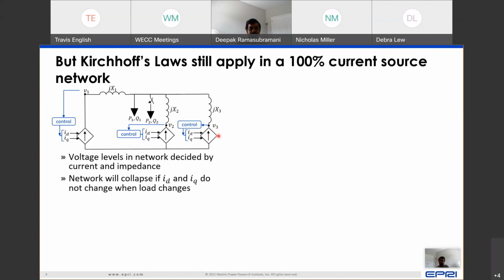But at the same time, if you have a change in the network, say something like a load increase, where you change the topology of the network, you change the properties of the network, and if you do nothing to change the current being injected into the network from the variety of sources, then there is a possibility that the network can collapse. That is primarily because you have much more impedance in the network, you don't have enough current being injected, and your voltage can collapse as a result.